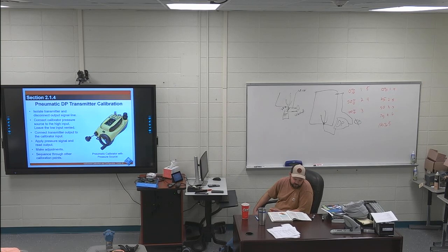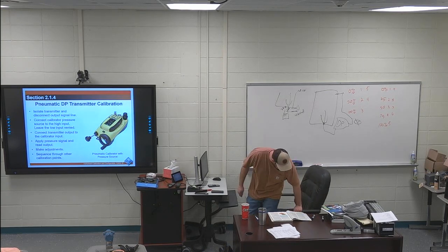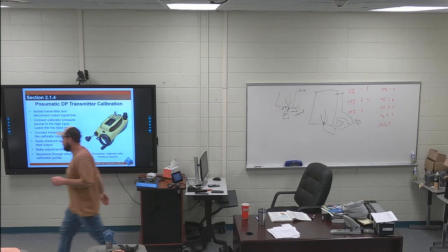215 temperature transmitters. Second paragraph, second sentence of 215. A bench calibration check can be performed on a bulb type instrument by providing a calibrated temperature control bath in which the bulb is inserted to simulate the process while monitoring the pneumatic output of the signal using a multifunction calibrator.